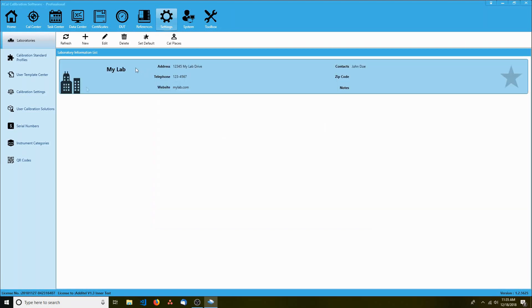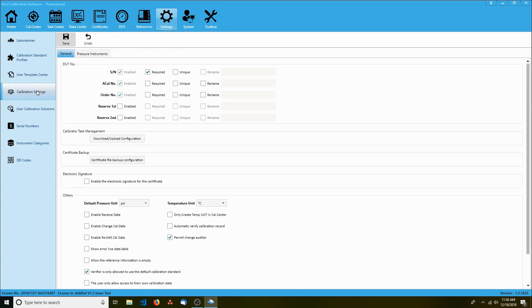Next, take a look at the calibration settings submenu. The first thing you're going to notice is a section called DUT number. The idea behind this is that there are a lot of numbers you associate with the devices you calibrate. For example, your DUT probably has a serial number, and it also probably is tied to a purchase order or a sales order. You may want to store those numbers in ACAL.